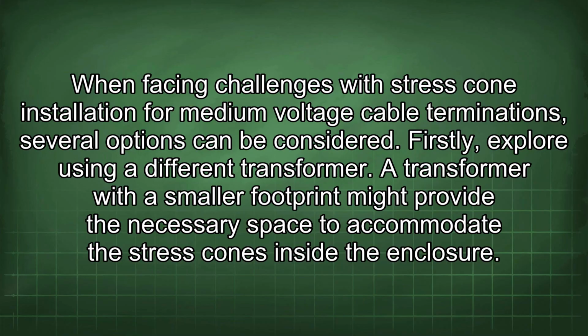When facing challenges with stress cone installation for medium voltage cable terminations, several options can be considered. Firstly, explore using a different transformer. A transformer with a smaller footprint might provide the necessary space to accommodate the stress cones inside the enclosure.